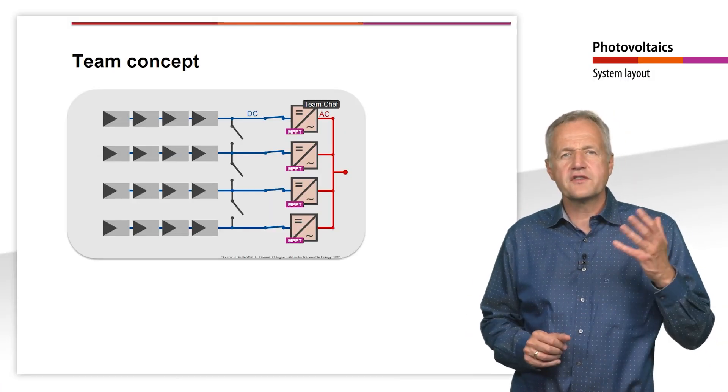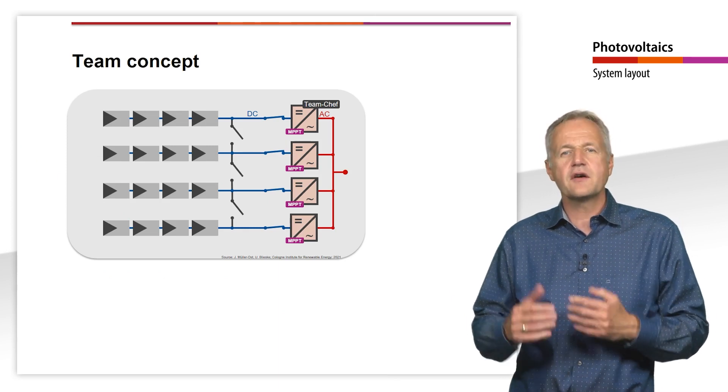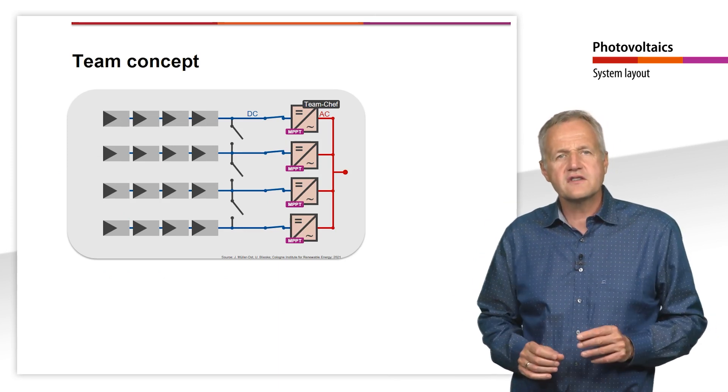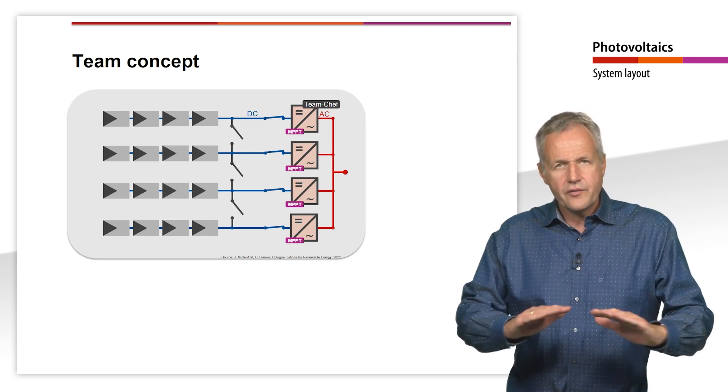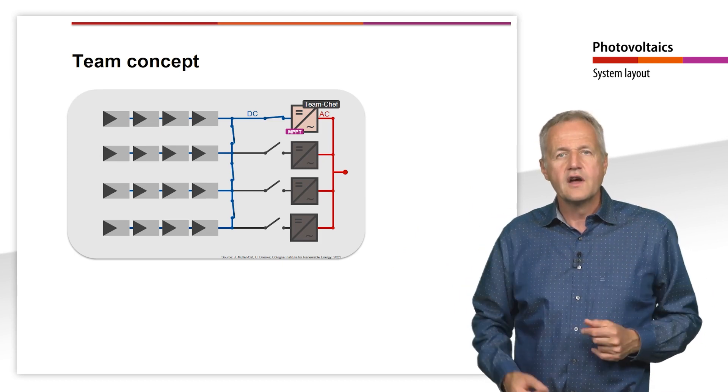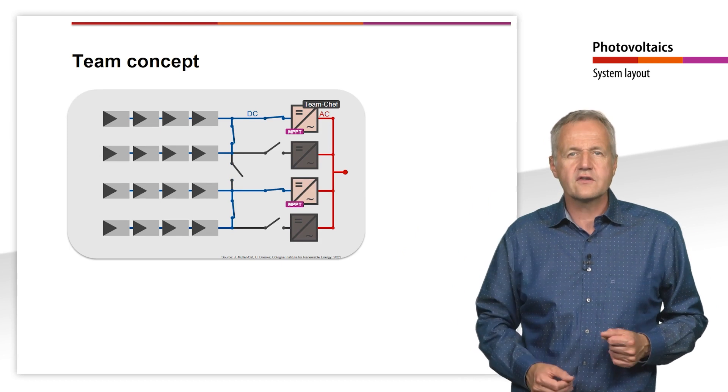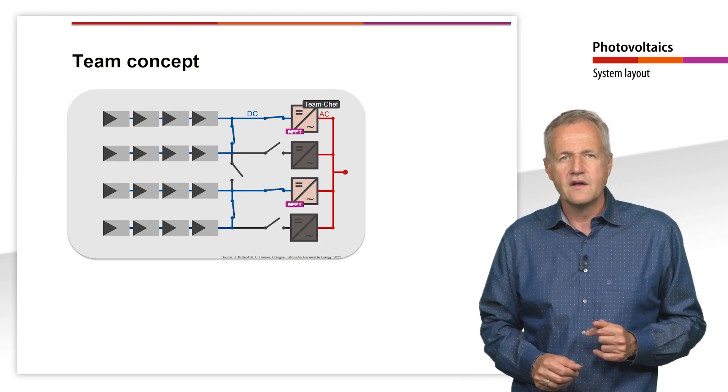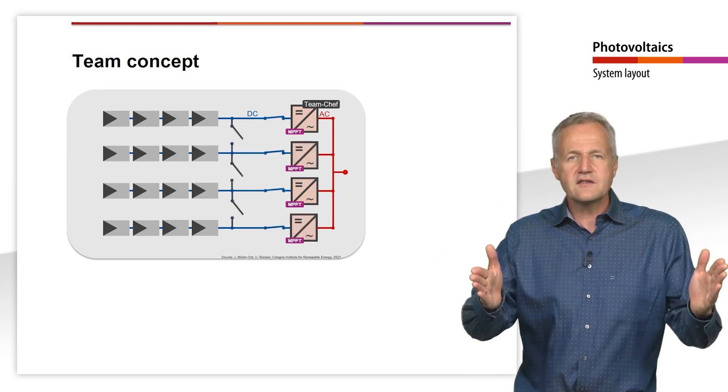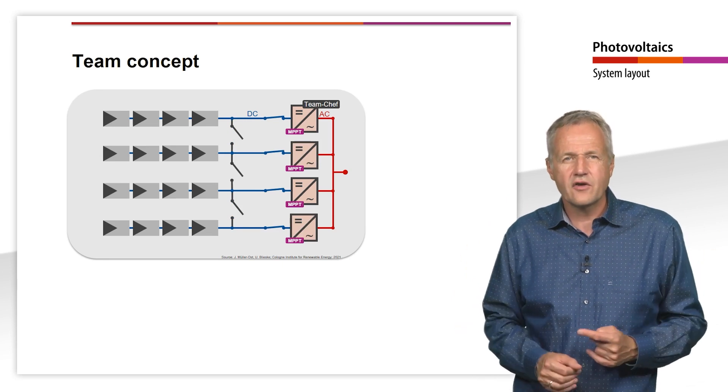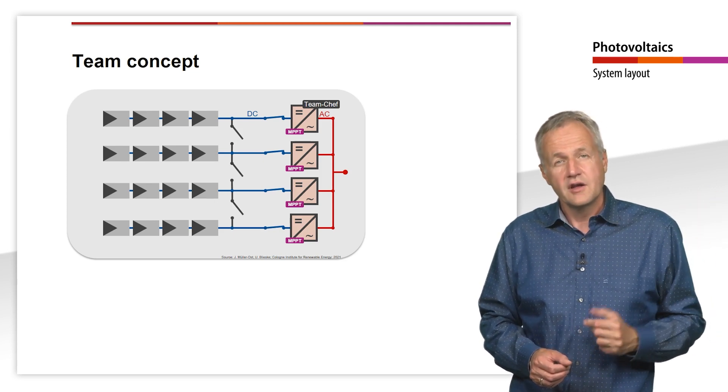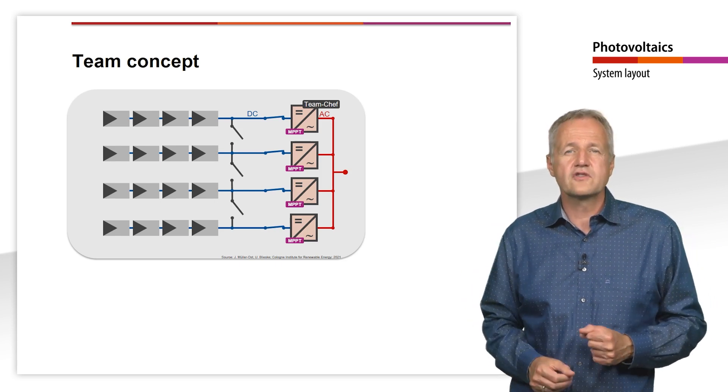In order to reduce the mismatch losses as well, the so-called team concept from SMA can be used instead of the master-slave method. Here, each string is first connected to its own inverter. One of the inverters is given the role of the team leader. At low irradiance, the team leader can switch the strings of the other inverters to itself and work alone. With increasing irradiance, it can activate another inverter so that each inverter takes over 50% of the generator power. If the irradiance increases even more, the number of connected inverters is doubled again until finally the entire system operates in string mode. In contrast to the master-slave concept, each inverter can control the operating point of its partial generator independently of the others. Thus, mismatch losses are reduced compared to the master-slave concept.